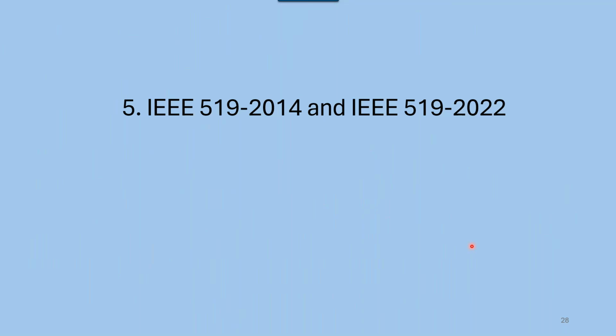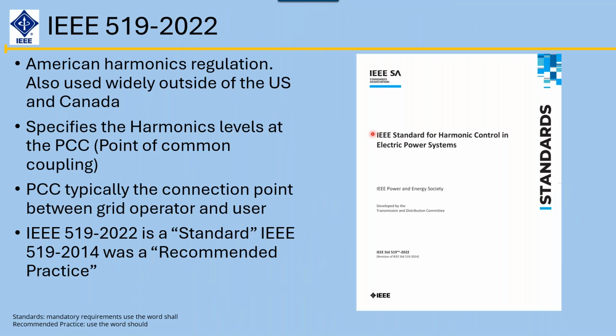All right, let's talk about IEEE 519-2022. This is a new standard. The 2014 version was a recommended practice. The way you can tell a recommended practice from a standard is that a standard will use the word shall, while a recommended practice will use the word should. So 2014 was a recommended practice, and 2022 is a standard, meaning you are supposed to follow it. They toughened up the standard.